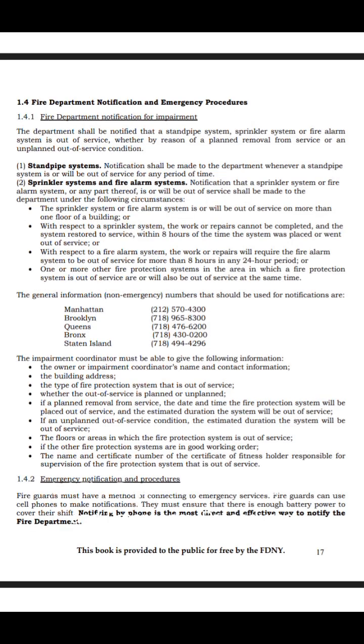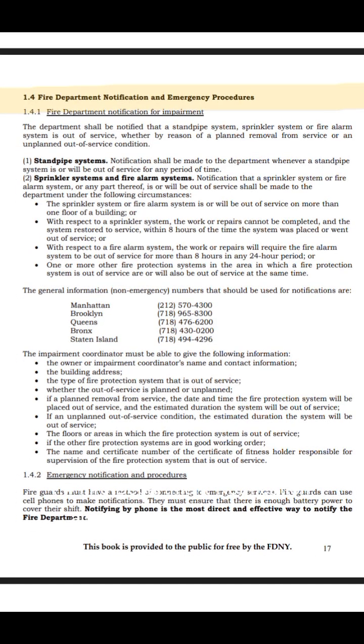1.4 Fire Department Notification and Emergency Procedures. 1.4.1 Fire Department Notification for Impairment. The department shall be notified that a standpipe system, sprinkler system, or fire alarm system is out of service, whether by reason of a planned removal from service or an unplanned out-of-service condition. 1. Standpipe systems. Notification shall be made to the department whenever a standpipe system is or will be out of service for any period of time.